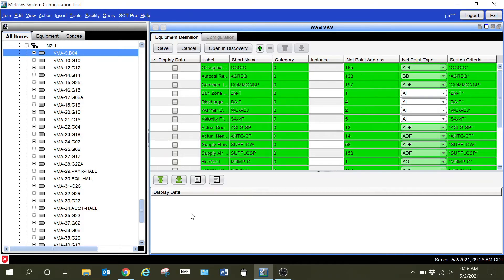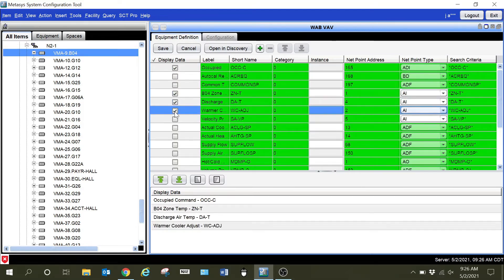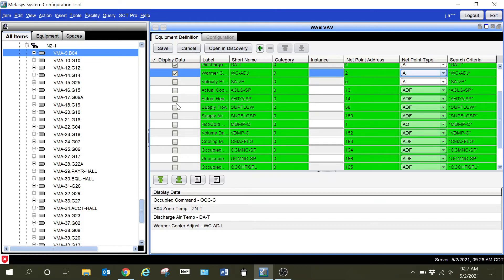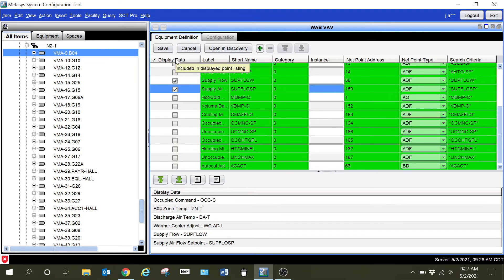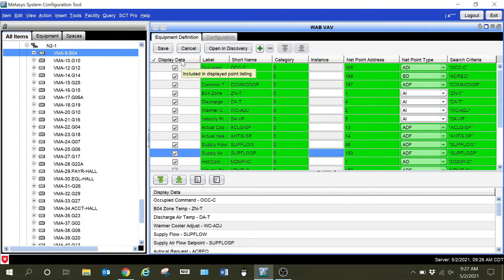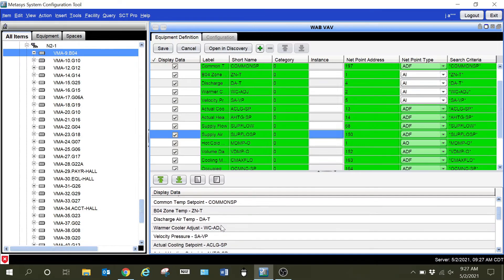I have my occupancy command and everything. This is where you're going to add in the points that you want to display in the system — you can move them around. I'm going to hit Occupancy, Zone Temperature, Discharge Temperature, Warmer/Cool Adjust, and so on. You can move them up and down by highlighting and hitting the up or down arrow, because this lower part shows the order in which they'll appear. I'll scroll on down and grab other set points — your flow, supply flow set point. You can also select all of them at the top. It may put things out of order, but you can simply highlight one and move it to where you want it to appear.